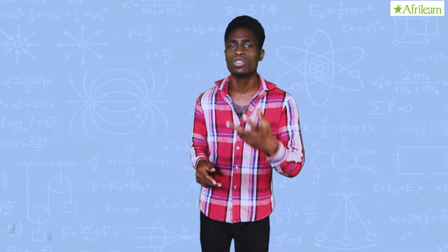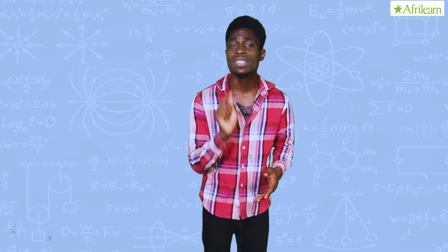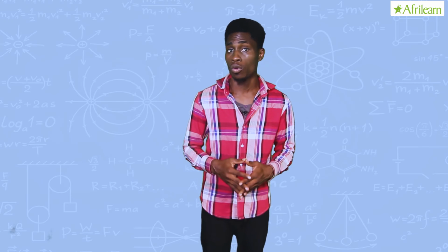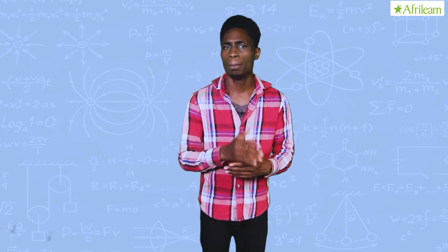Now, the state of charge of a lead acid cell can be ascertained by measuring the specific gravity of the electrolyte with a hydrometer. In case of cap lamp batteries, the specific gravity may be higher than stated above because a specific discharge characteristic is required in cap lamp batteries.